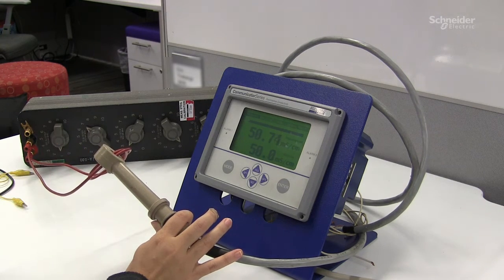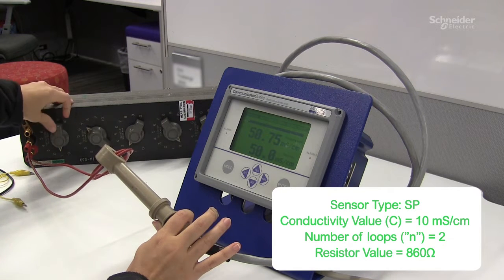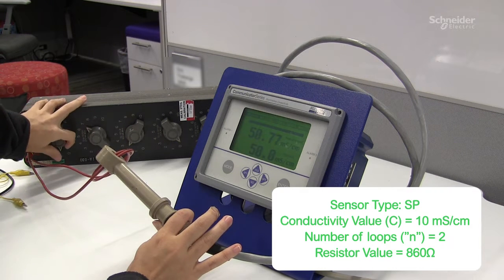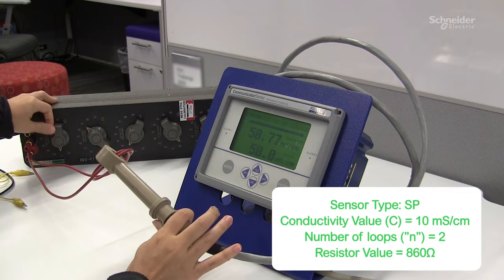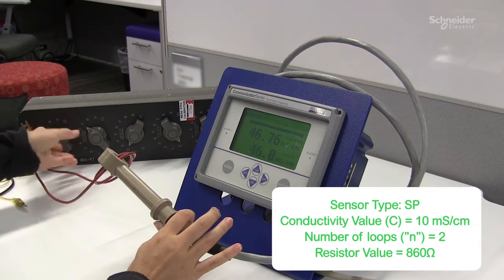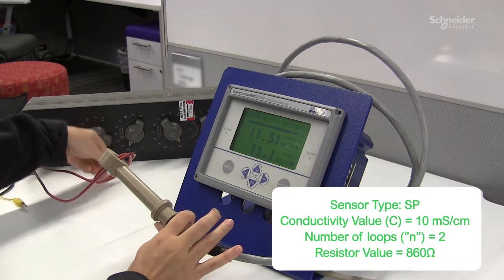And now I'm going to simulate a different conductivity. I'm going to move to 10 millisiemens and for that I believe I require 860 ohms. And again these values are found with the formula we just discussed.